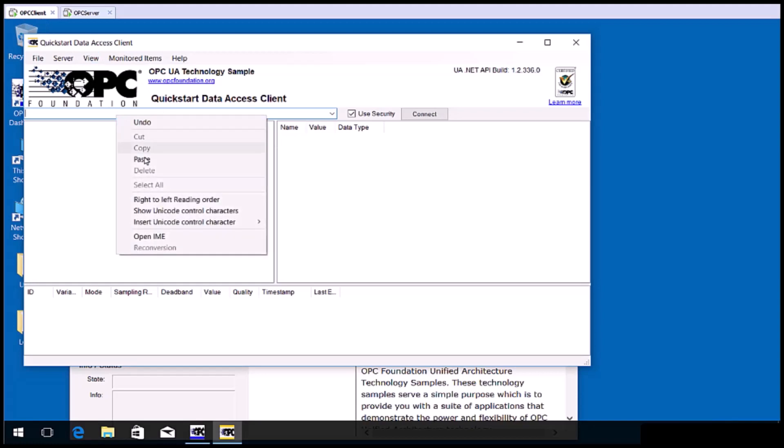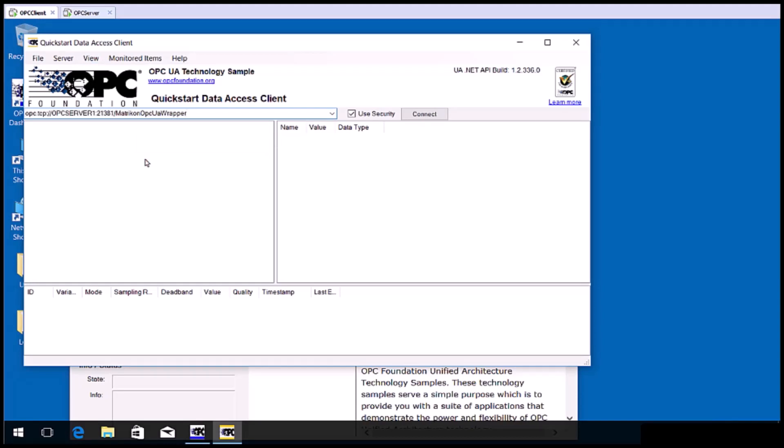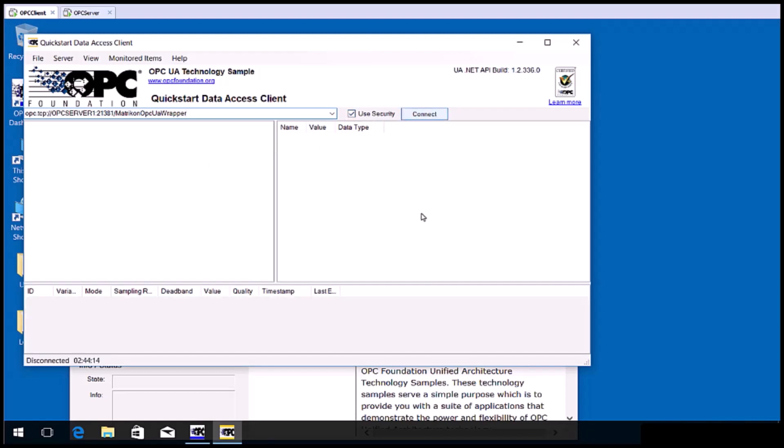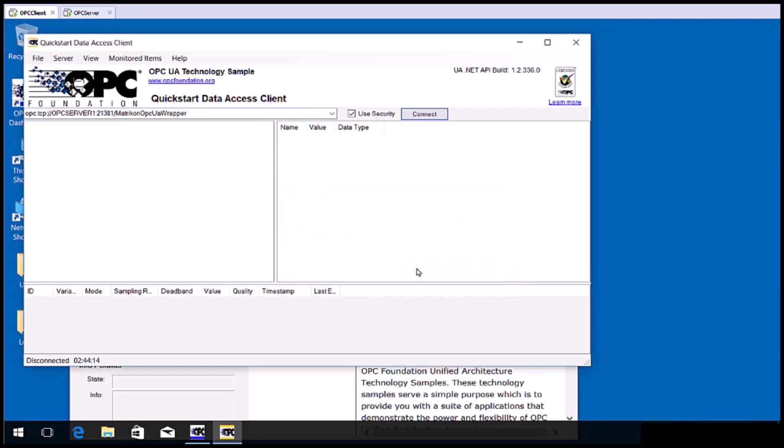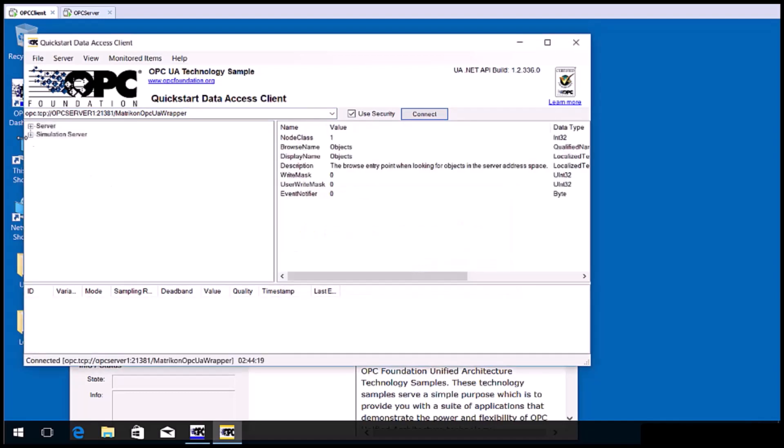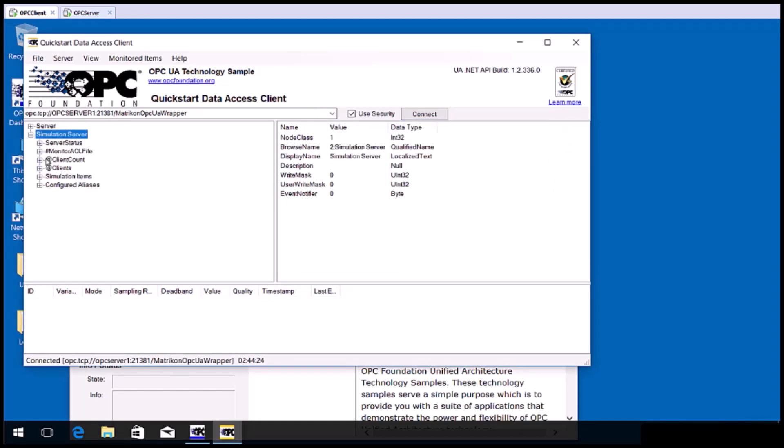Go back to the OPC UA client computer and open the OPC UA client. Paste the URI and retry the connection with use security enabled. Now that the certificate is in the trusted area the connection succeeds. And you can now browse the classic OPC DA server using your OPC UA client.